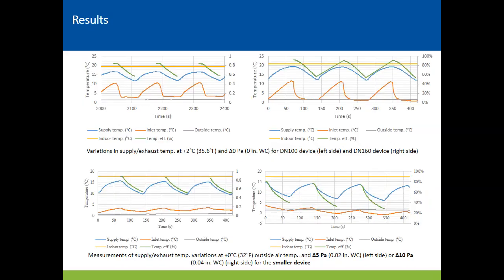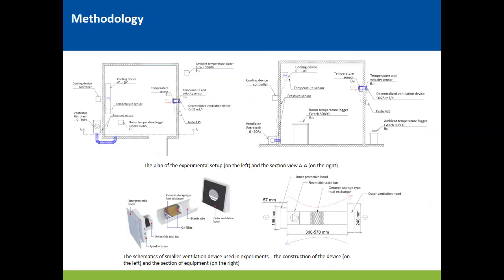The other thing is, what about certification? So the manufacturer can measure according, they claim, to the European standard. Is there a certification body like we have here in North America, AHRI? I think they are certified according to this EU standard. But this EU standard doesn't state that you need to measure this efficiency at different pressure differences. They just install two devices in something similar to what we did in this climatic chamber, but there are no pressure differences from outside to inside.